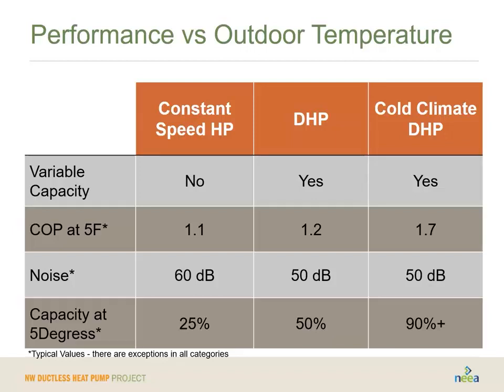Now look to the right-hand column at cold climate ductless heat pumps. They have 160% of the COP of a constant speed heat pump. They're quieter, and they're capable of producing 90% of their capacity at 5 degrees. The standard heat pump is right down the middle between these two. We'll talk a little bit more about this, but effectively, one way to say it is if you live west of the mountains in the Pacific Northwest and you're not at a high elevation, a standard ductless heat pump is probably going to satisfy most of your needs. If, however, you are in an inversion zone, at a higher elevation, or east of the Cascades, cold climate ductless heat pumps are really going to be the thing that gets the job done for you.